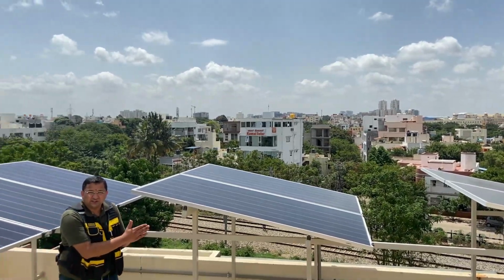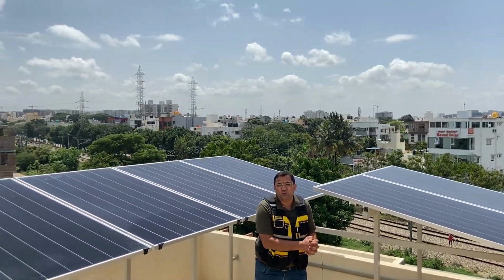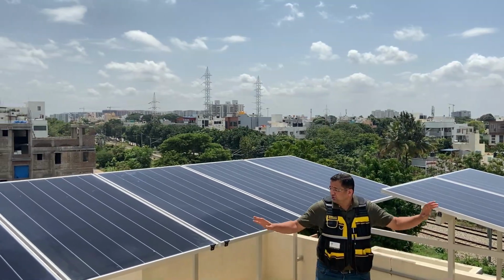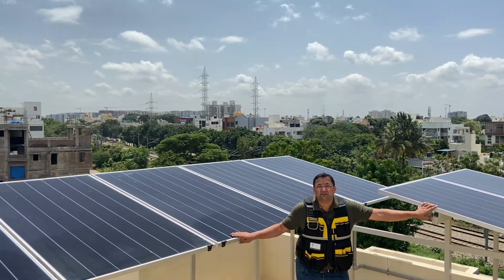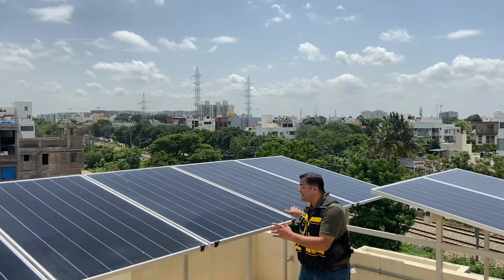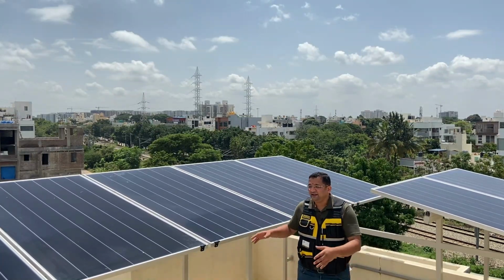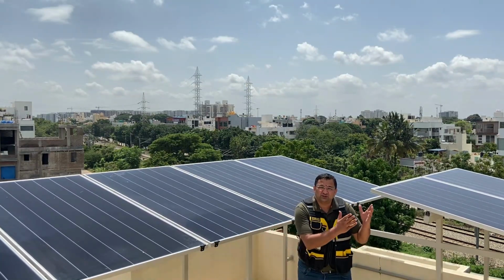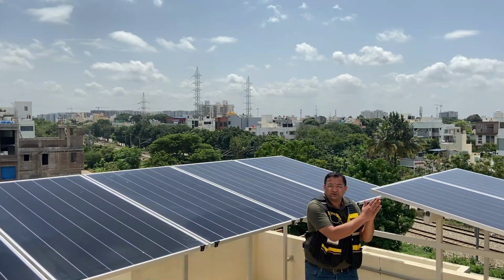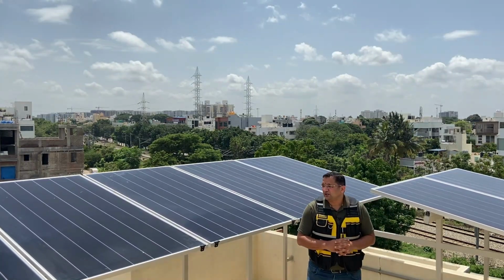The charge controller for this system takes 145 volts of open circuit voltage. These 10 panels are made into 5 strings, with 2 panels connected in series each. All 5 strings are taken into the array junction box, and from there to the charge controller, which we will shortly show.